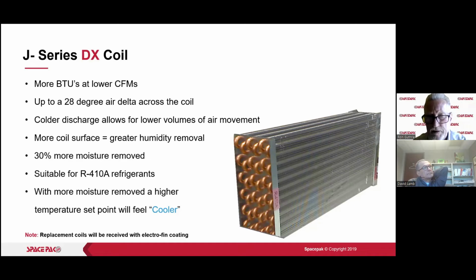Less of the BTUs that we remove are going to be sensible, so we have better dehumidification. That means we've got more latent heat removal, but we do want to make sure that we cover the sensible loads in our home or building. Okay, so just make sure you're not shorting yourself on BTUs. Look at those readings on the unit. The unit that has more BTUs is closer to the nominal tonnage. So we remove 30% more moisture.